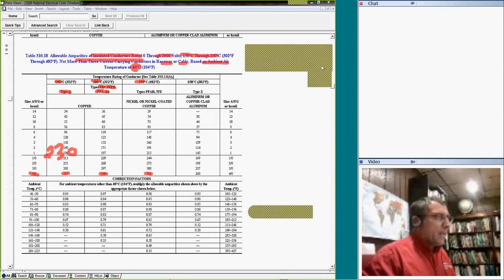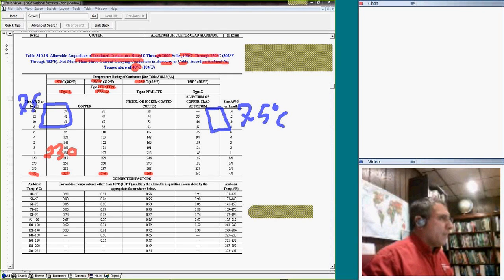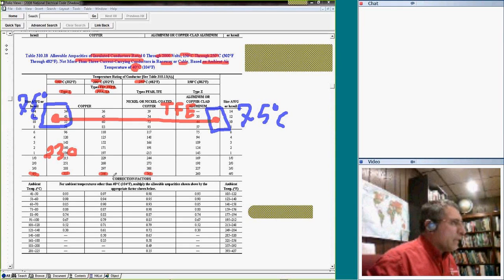But this doesn't mean you can carry the same amount of amps. For example, we always buy lugs. Here's the lug, here's the lug. This lug is rated for 75. You can't find lugs rated more than 75 for low voltage. And I need a conductor to tie these two lugs together. So here's my conductor landing on these two lugs. Let's say this conductor is a TFE conductor, rated for 250. This conductor is 4 aught, TFE, so it's supposed to be able to handle up to 361 amps, right?